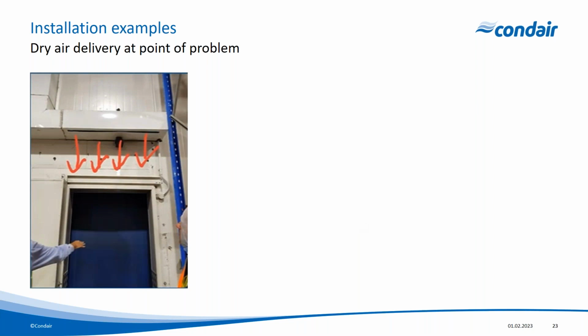So once we've got this dry air, there are various ways that we can deliver it and use it as well. In this example, you can see that we've got a duct that's being fed by a dehumidifier. And this duct, we've got a delivery slot for the air, and air is traveling over this doorway. And again, we're doing sublimation to get rid of any ice buildup. Ice was interfering with the mechanical aspects of the door, with the opening and closing mechanism, and interfering with switchgear. So by just putting that blanket of dry air over that doorway, we sublimate the ice away. Again, we're taking that ice from its solid phase to its gaseous phase without going through the liquid phase.